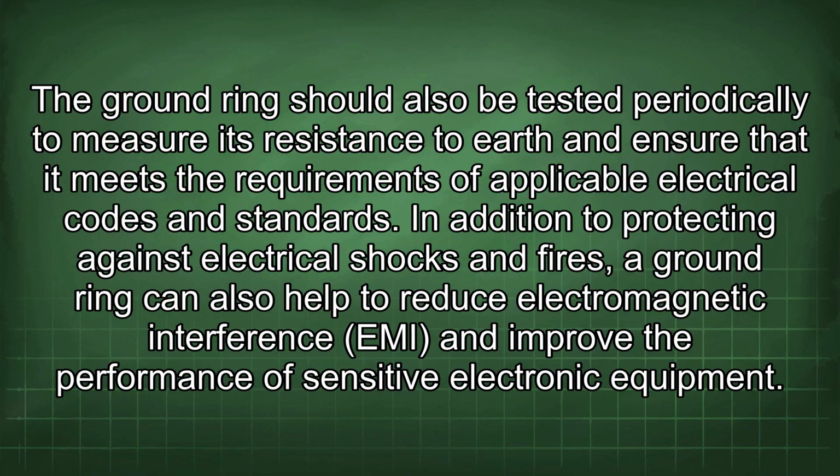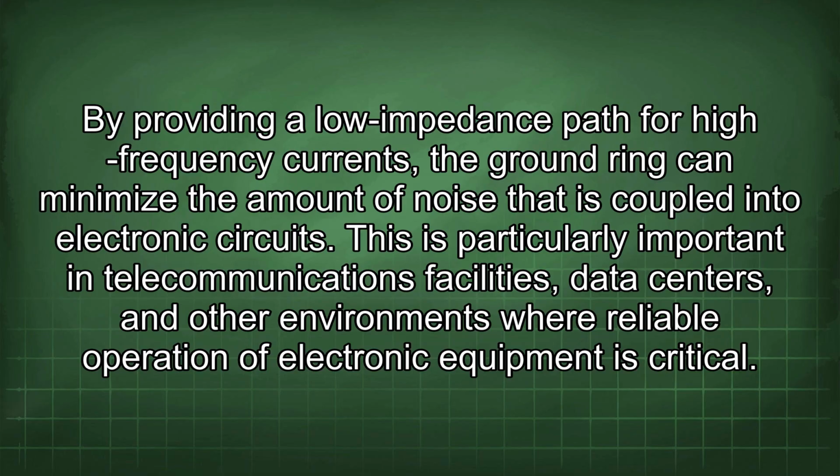In addition to protecting against electrical shocks and fires, the ground ring can also help to reduce electromagnetic interference (EMI) and improve the performance of sensitive electronic equipment. By providing a low impedance path for high-frequency currents, the ground ring can minimize the amount of noise that is coupled into electronic circuits.